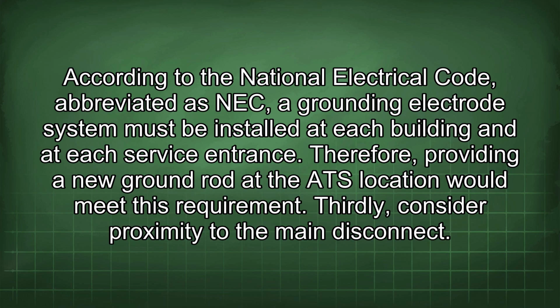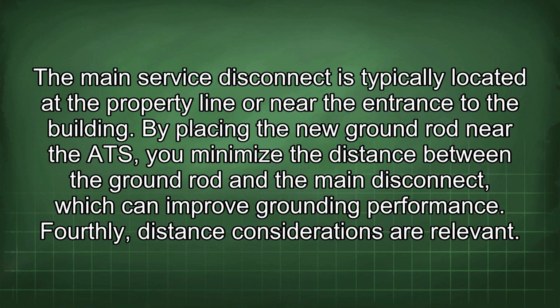Thirdly, consider proximity to the main disconnect. The main service disconnect is typically located at the property line or near the entrance to the building. By placing the new ground rod near the ATS, you minimize the distance between the ground rod and the main disconnect, which can improve grounding performance.